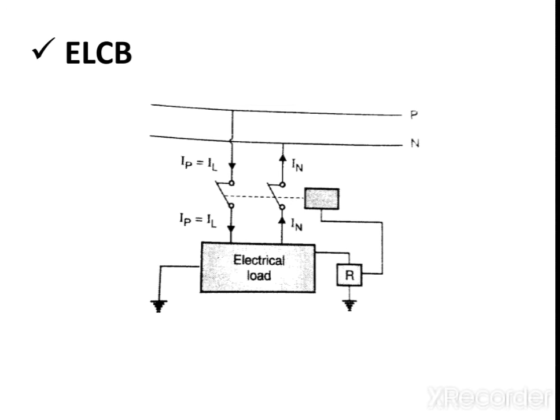our body can conduct this small amount of fault current. Due to this, it will cause electrical shock, or sometimes it may cause an electrical fire. Sometimes it may even cause death. To avoid these types of dangerous electrical conditions, we use ELCB. ELCB are protective devices to provide protection against ground fault or improper insulation failure.